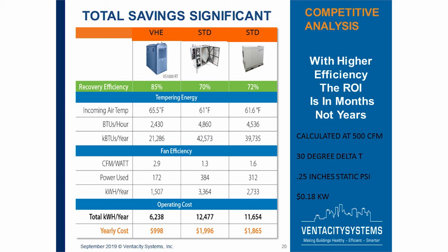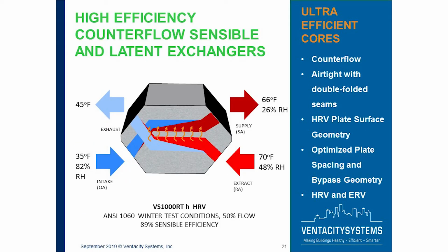Cost per watt is exceptional as well when you have ECM technology, the tempering of the air, and the fan efficiencies, and you can see the yearly operating cost of some competitors of ours versus one that's 85% efficient. That's the counterflow heat exchanger we talked about, and the slide is showing how you're bringing in 35-degree Fahrenheit air through that core. It's picking up the 70-degree air that's coming back, transferring that energy, and providing 66 degrees into the space.